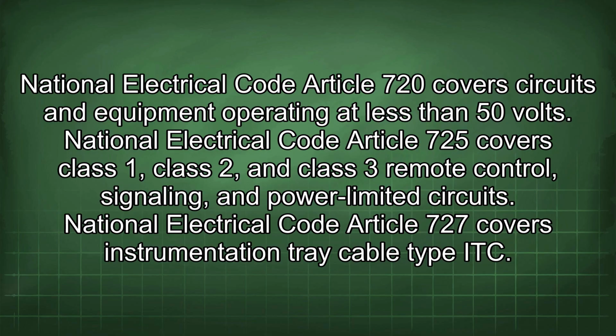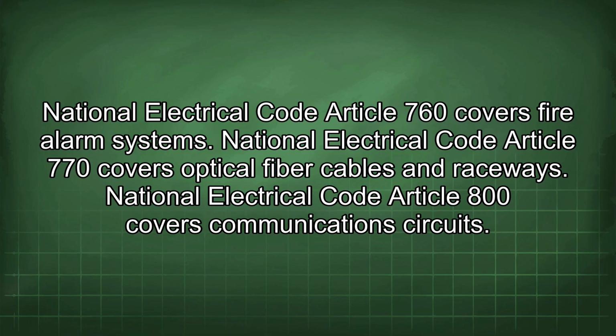National Electrical Code Article 720 covers circuits and equipment operating at less than 50 volts. Article 725 covers Class 1, Class 2, and Class 3 remote control, signaling, and power-limited circuits. Article 727 covers instrumentation tray cable type ITC. Article 760 covers fire alarm systems. Article 770 covers optical fiber cables and raceways. Article 800 covers communications circuits.